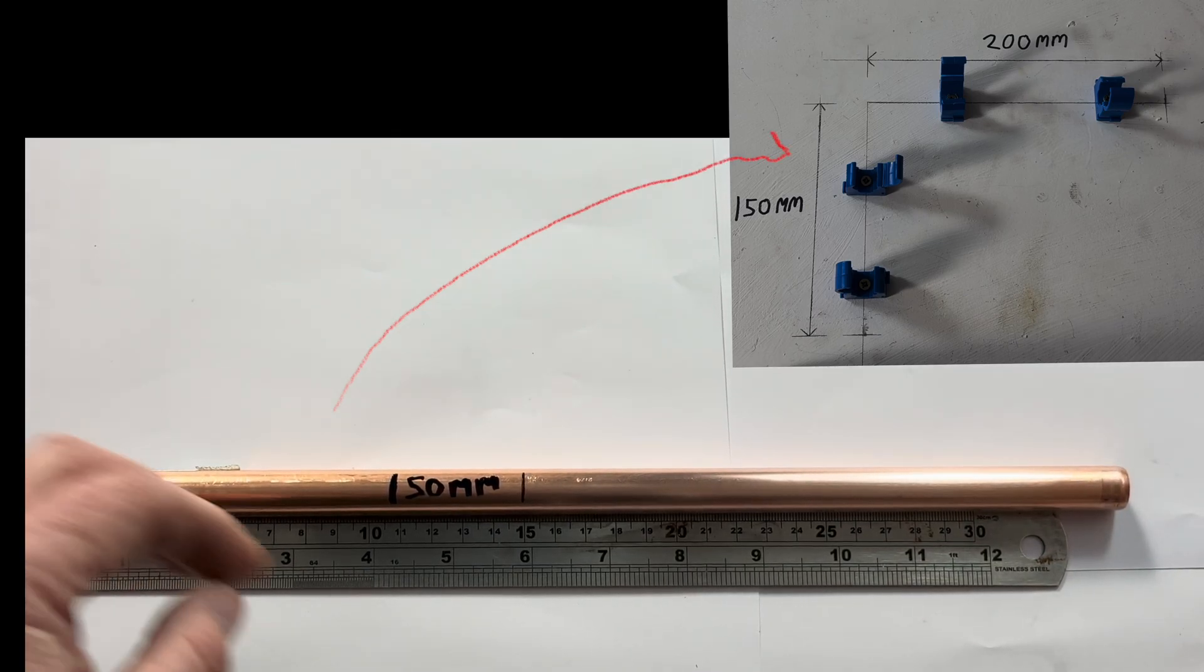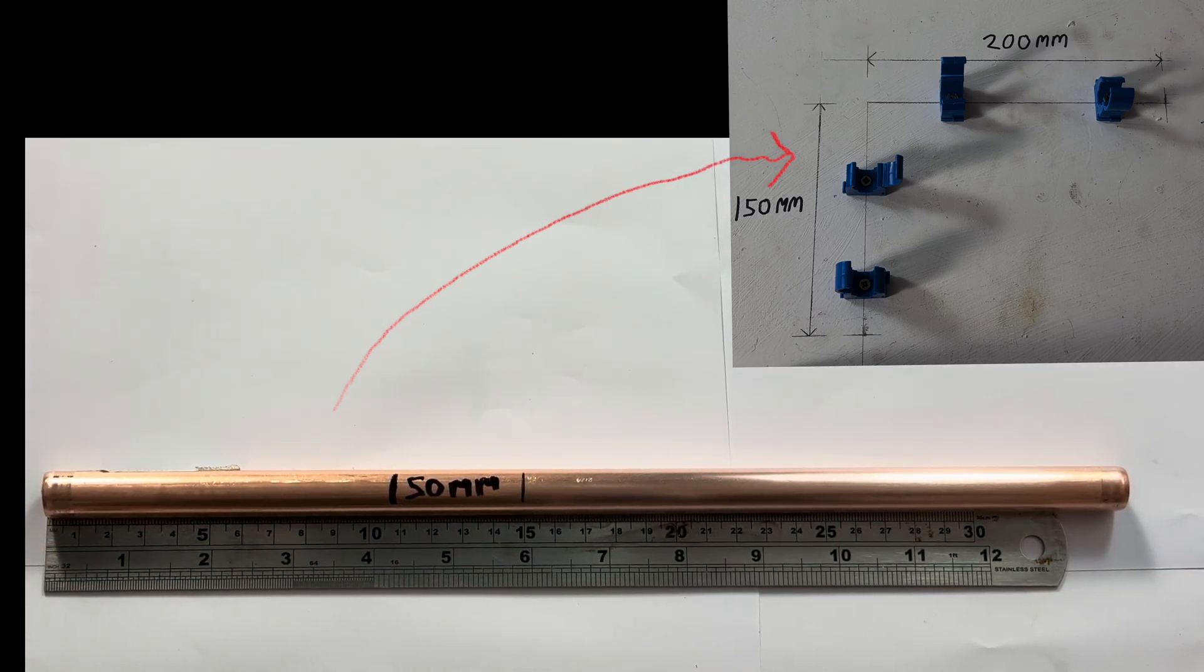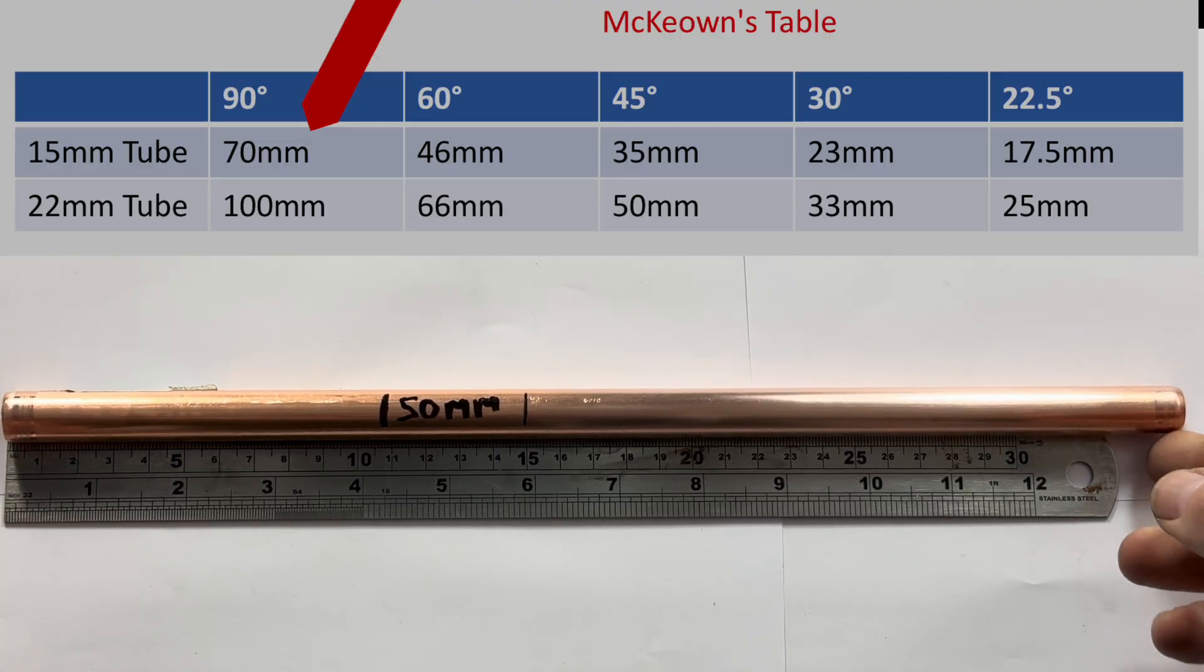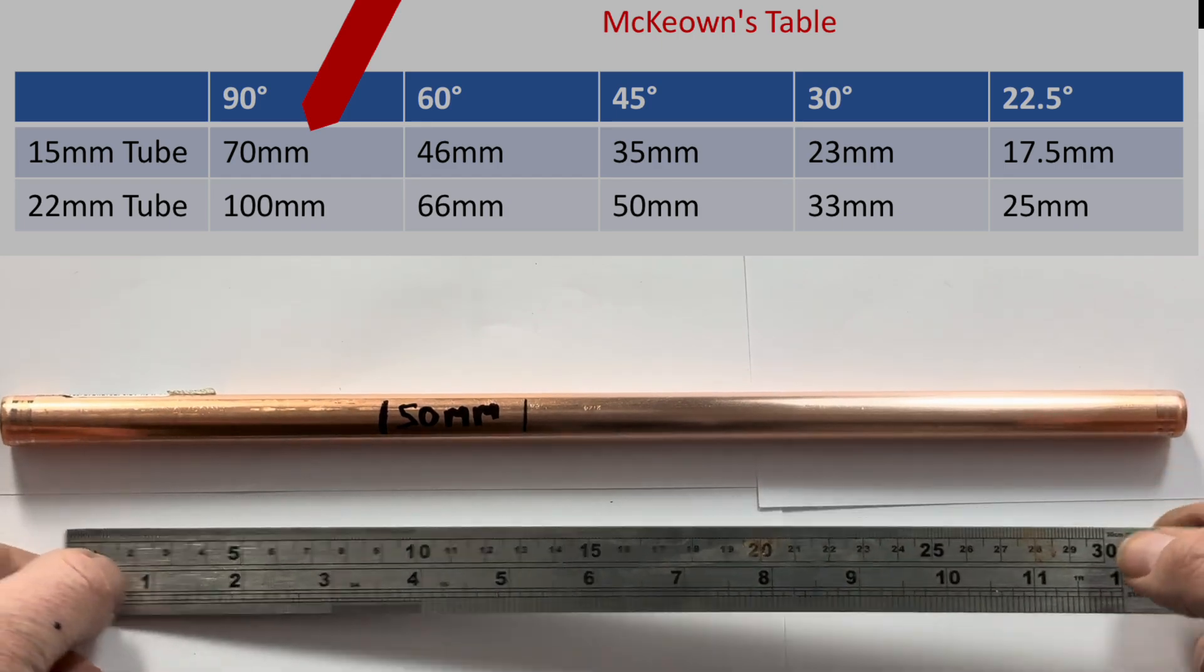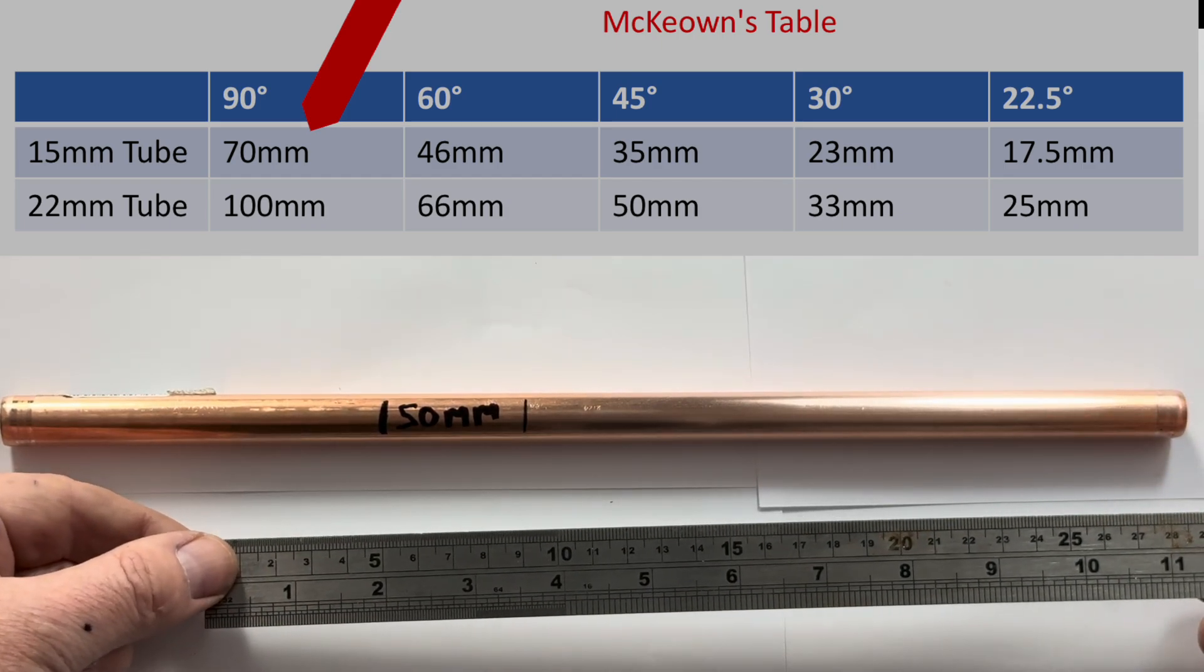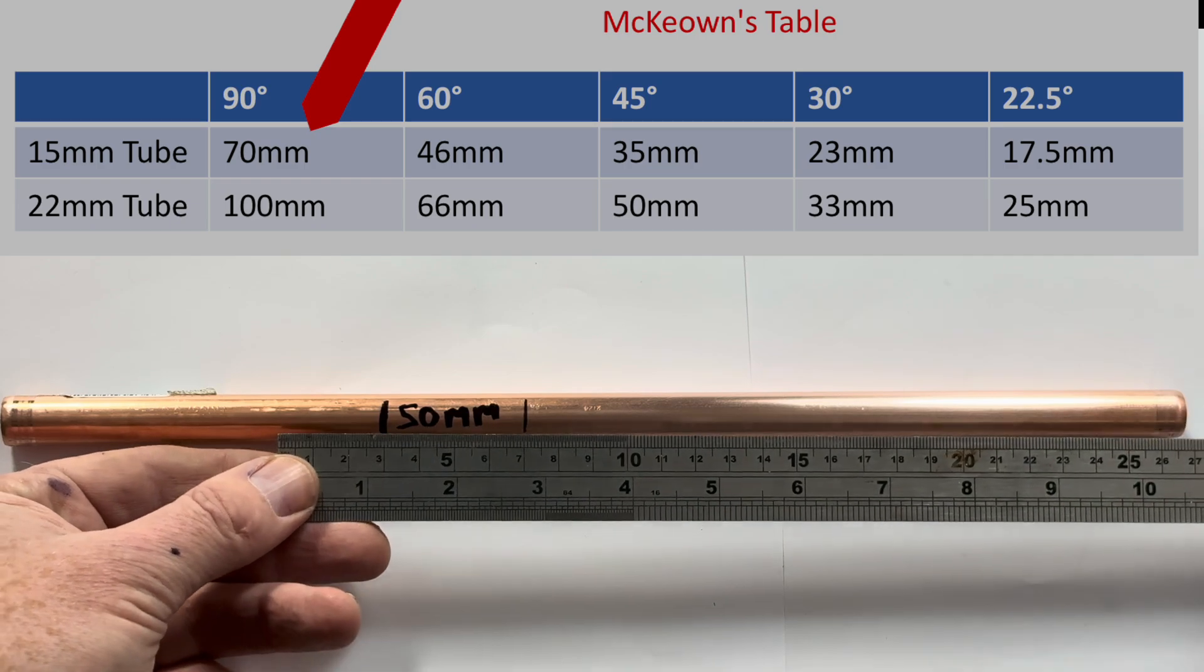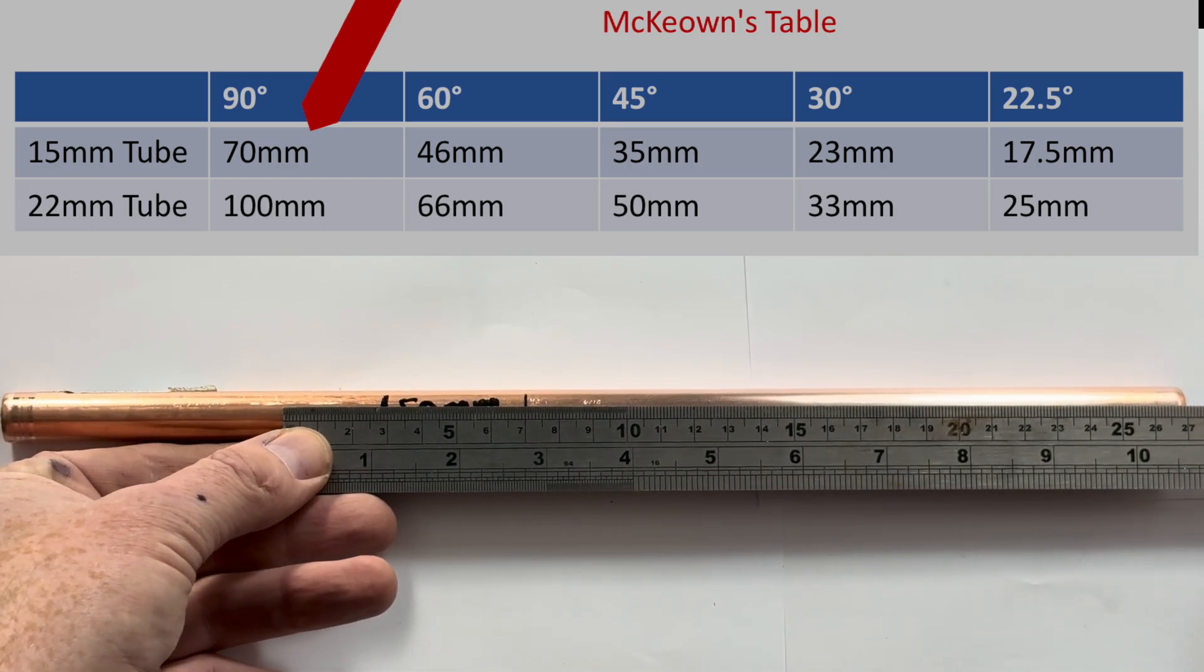I've measured 150mm like that. So, then looking at the McKeown measure back chart, we need to measure back, because we're bending 15mm pipe 90 degrees, we need to measure back 70mm.